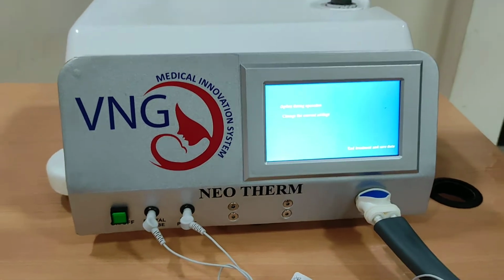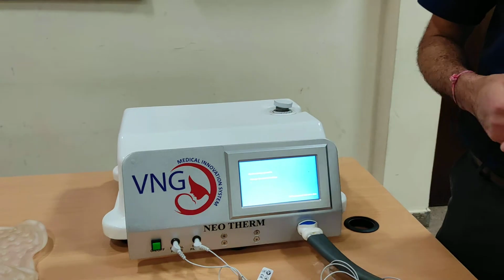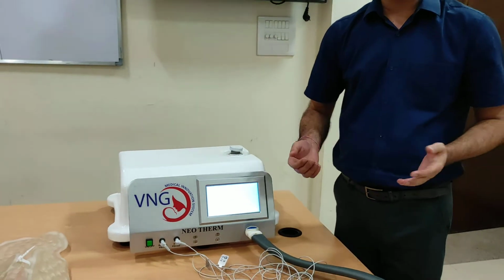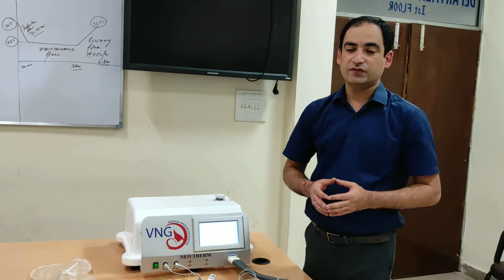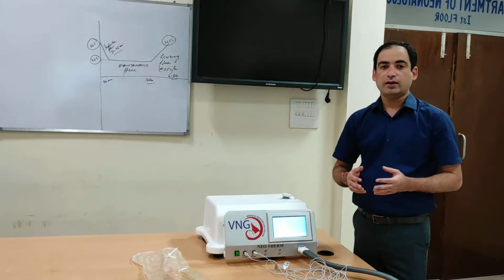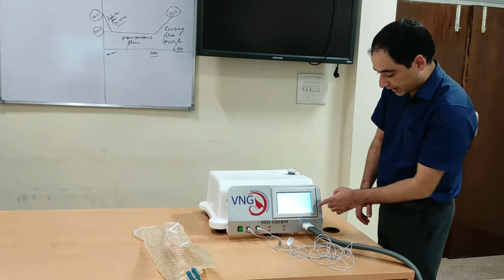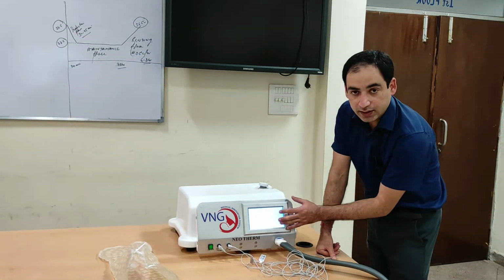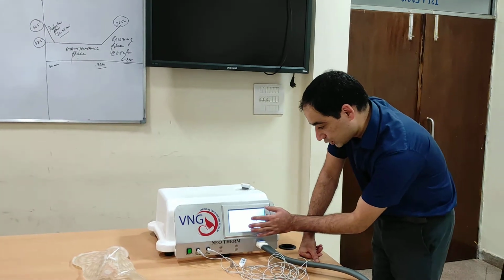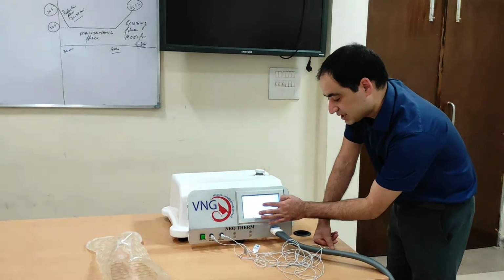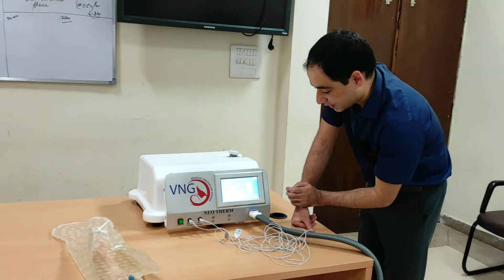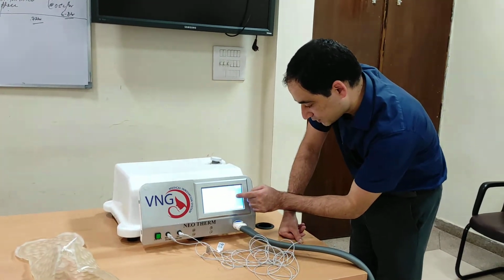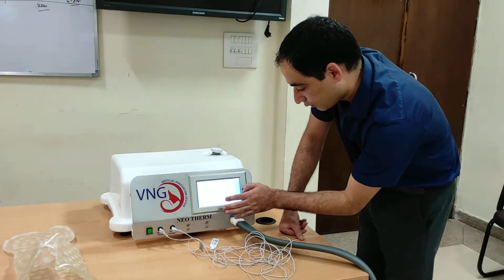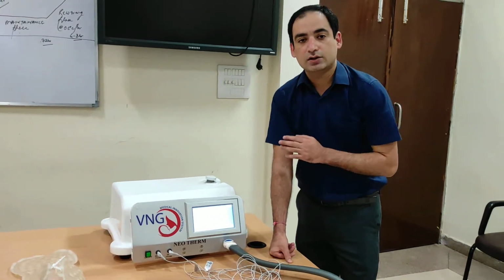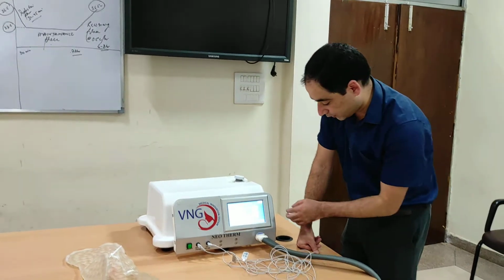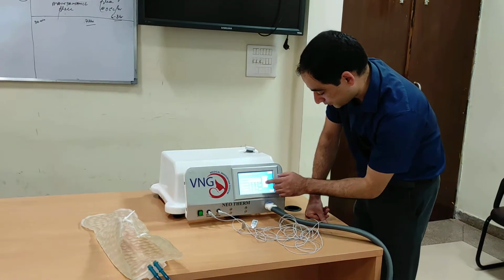If suppose the baby worsens, there is bleeding despite giving blood products, there is severe PPHN, or the baby is moribund where the physician thinks that baby will not survive, you can abandon cooling before 72 hours. In that case, you will go to the options and then this screen will get displayed. In this screen, you can see that there is an option called change the current setting. So we'll go to change the current settings and the duration from 72 hours will become 0. Once you set it 0, it will stop cooling. So you can interrupt cooling in between if the condition of the baby is so.